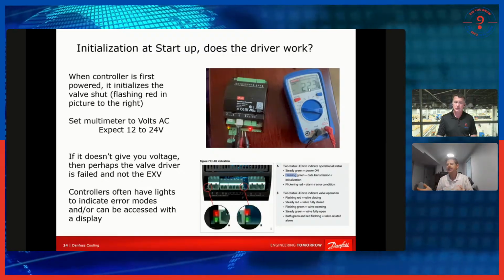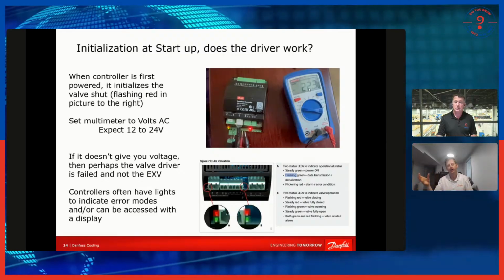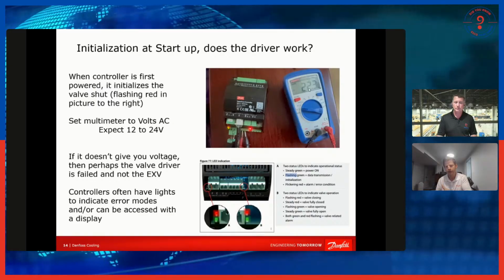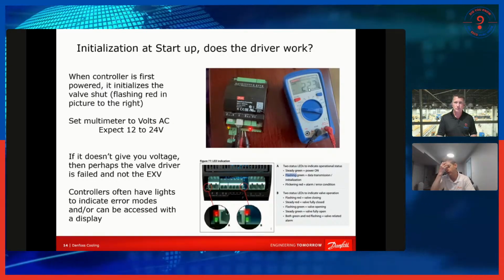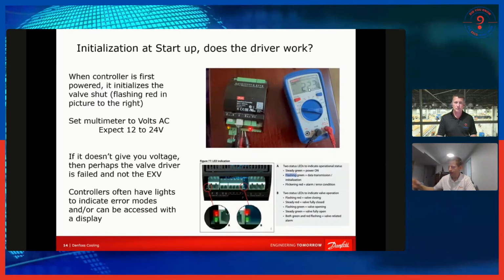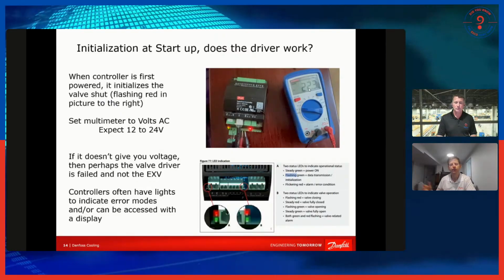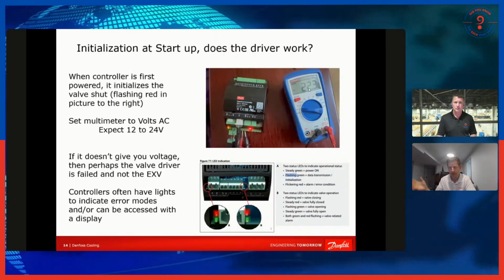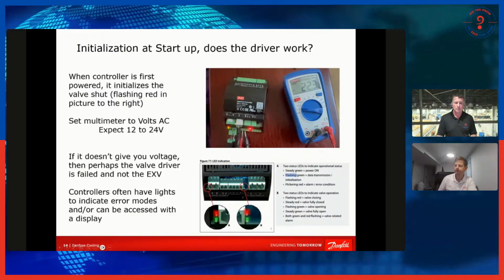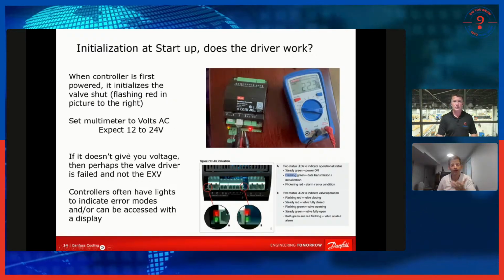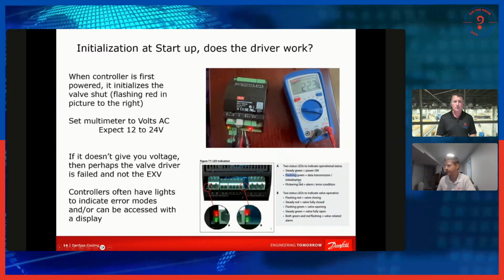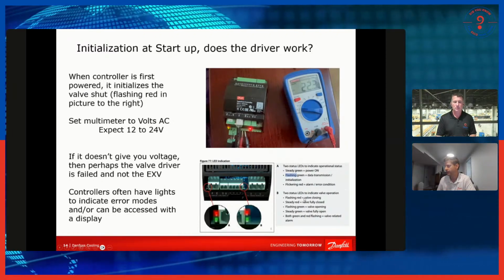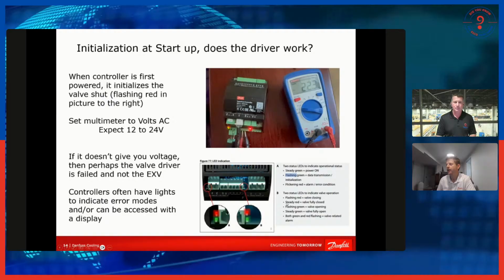So it gives you an indication that the driver and the board itself isn't burned out. You didn't get a burn inside the control board. There wasn't a lightning strike and a power surge to the controller that burned it out. And knowing more about the controller itself can help, because there are all kinds of different flashing lights that tell you if you've got problems.